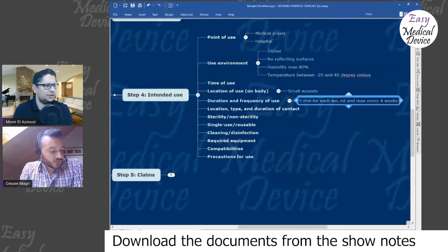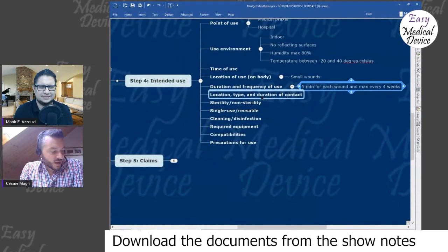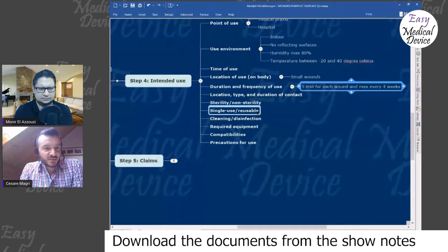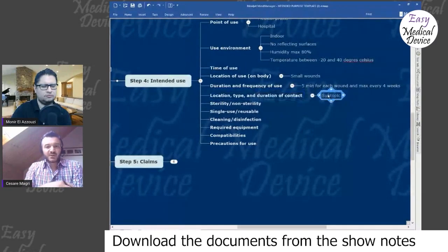Okay, I think we are creating a great intended purpose here. What about the rest? Whether you specify, even if it's maybe redundant, that the device is not intended to come into contact with the patient - just to make it clear that one should not use it in contact, but just with a certain distance. Minimum distance of 3 centimeters, let's say. This is nice for the auditor, that he knows there is no contact.